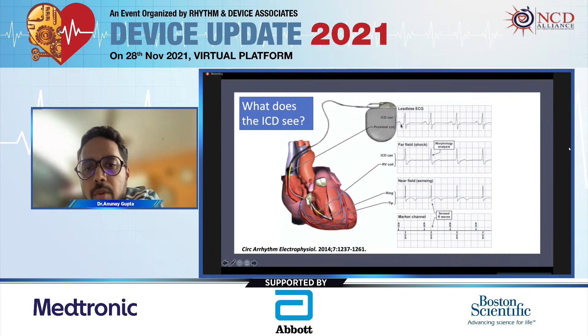So whenever a patient comes to us with a shock, first of all, the thing we have to see is the clinical scenario, and then we have to ask for stored EGMs. Then if we find there is a tachyarrhythmia, it can be either an SVT which has been inappropriately detected as VT, or a VT-VF which has been appropriately detected. In that case, what we have to do is stop the arrhythmias.